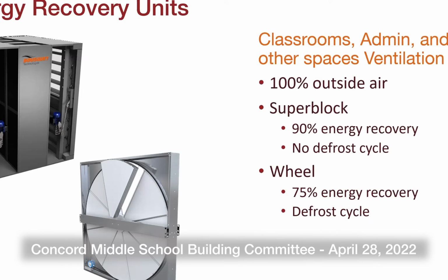But so it'll be 50% mixed air? I can pull up my calcs. I think one unit is 3,000 over 5,000, so that's 60%. Another one is 3,000 over 6,000, so that's 50%. And I can't remember what the third one is, but they vary in that 40 to 60 range. We can go over that more - again, that's more in the weeds. We'll get there on the sustainability subcommittee.